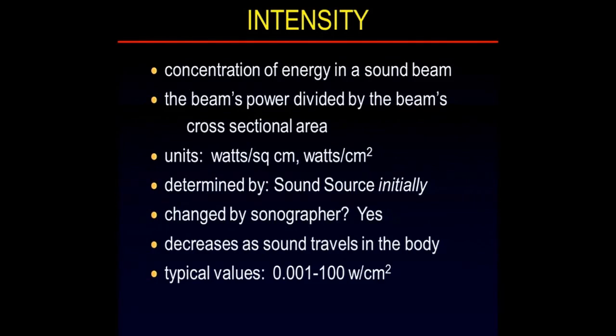The strength of the sound beam is determined initially by the ultrasound system. As sound travels, it gets weaker and weaker and weaker, and you can change the initial intensity of the sound beam. There's a knob on your machine called output power. And what you do by adjusting the output power is you change the initial level of intensity created by the transducer. The typical values have a very broad range of about 1/1000th to 100 watts per centimeter squared.